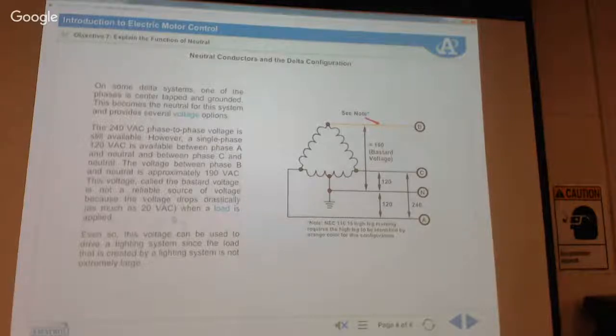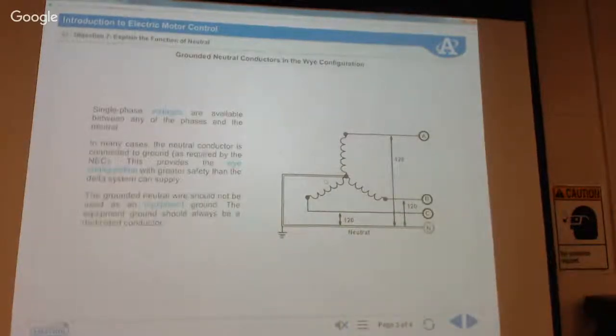And you're grounding your equipment because it can build up a charge. You're grounding your equipment for safety because, well, let's just say this is the inside of a transformer, right? It is the inside of a transformer. And you don't bond the outside metal box. If this wire comes loose and touches that box and it's not got a bonded ground, current won't flow and it won't blow the breaker, which means if somebody touches it, they'll become the breaker or fuse, whatever you want to call it.